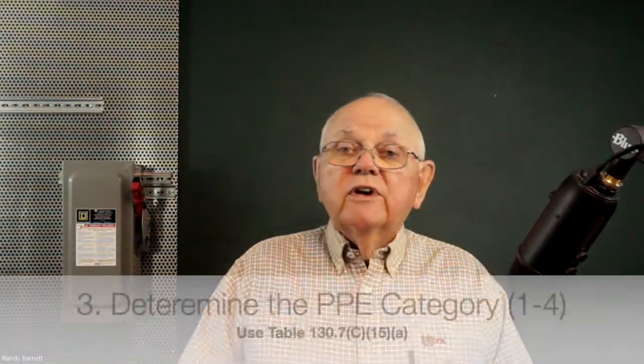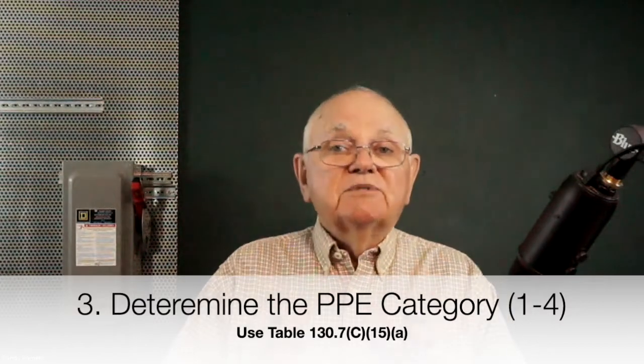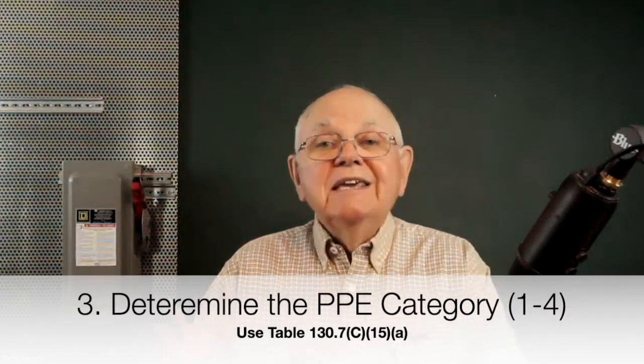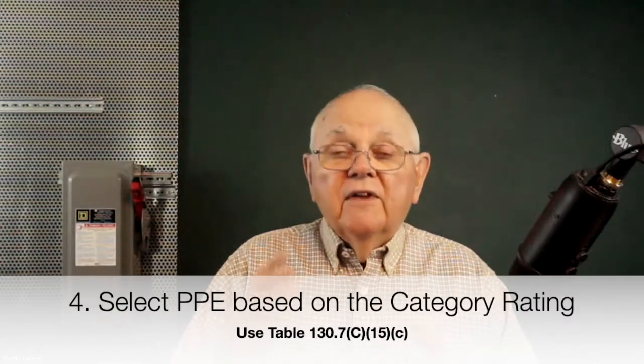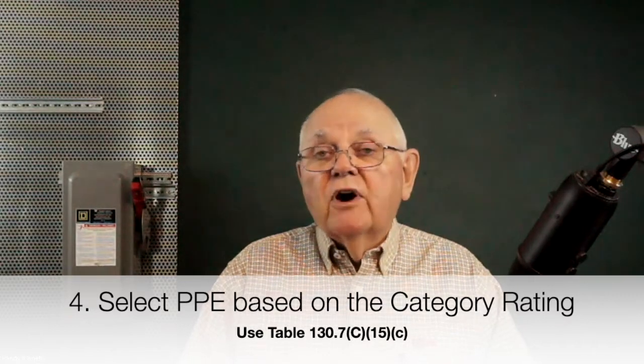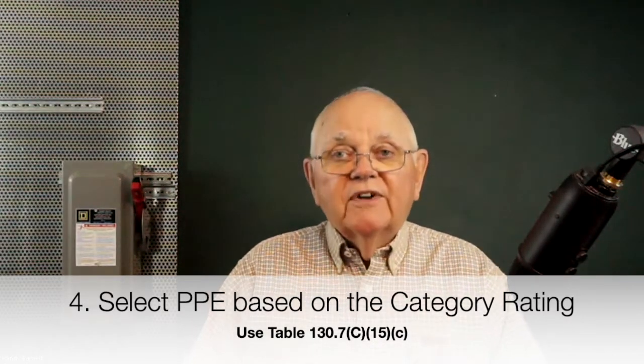If there is, or we feel that there is, for whatever reason, we go to another table, and it's going to tell us for that specific equipment what PPE category and what the arc flash boundary will be when we perform that particular task. We have to meet 2 parameters. We have to make sure that we're below the available fault current, and we are within the specifications for fault clearing time. You can do those on your own. Then the final table we will go to will tell us for a particular category what specific clothing we must wear. So that's it. Spend some time in your NFPA 70E.